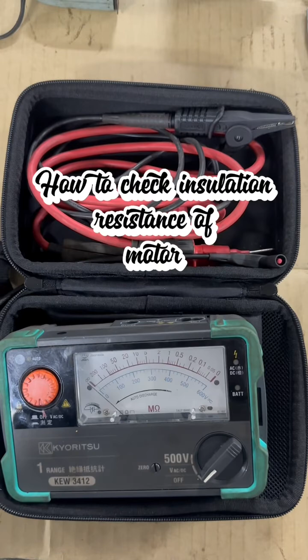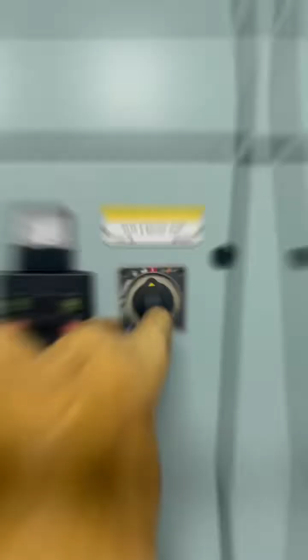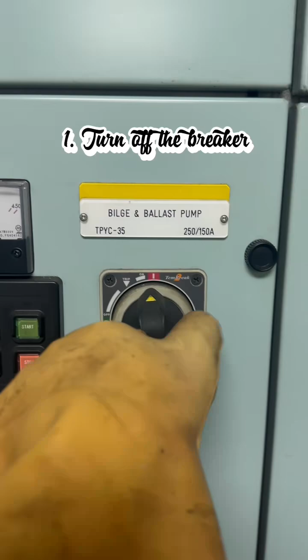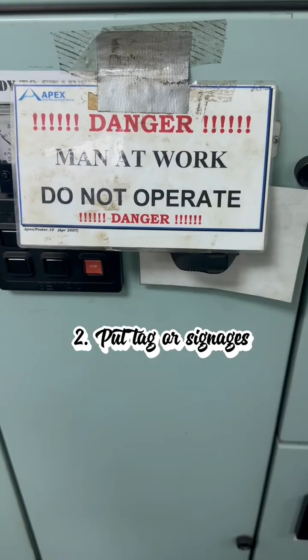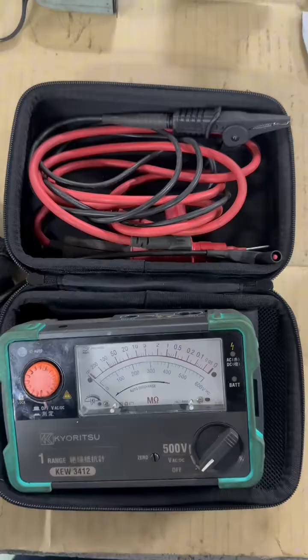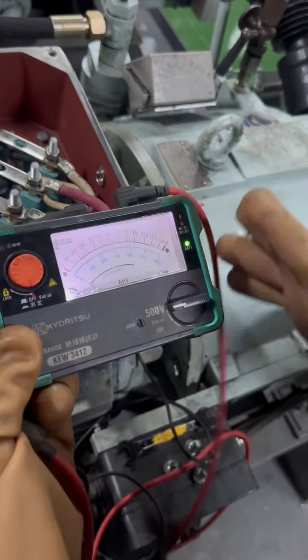Number 1, check the insulation resistance. How to check the insulation resistance of the motor? First, turn off the breaker or the power supply. Put tags or signages. Then, prepare the insulation resistance tester. Set to 500 volts. Then clip the black probe to the body of the motor or ground.